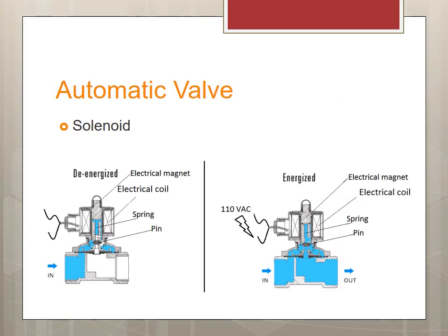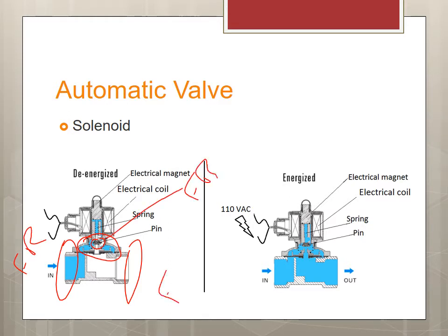When the solenoid is de-energized, we need to control a small amount of fuel at a small orifice. It's easy to put a pin and shut off the fuel at that small orifice. Even though the inlet and outlet are very large, the flow rate is the same throughout — so at the small orifice the velocity goes really high. We drop the pin perpendicularly, and if we counteract the flow in that small orifice area we shut off the fuel completely. When energized, it opens and the flow goes as intended.